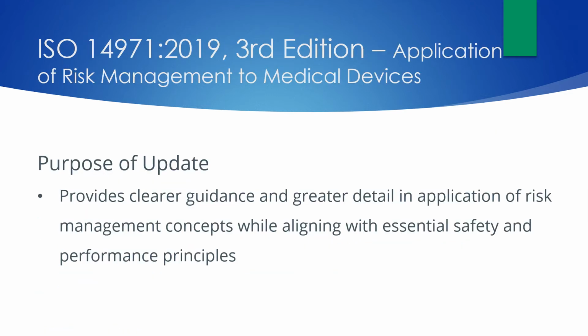The ISO standard 14971, which is the application of risk management to medical devices, was updated to its third edition in 2019. The purpose of the update was to provide clearer guidance and greater detail in the application of risk management concepts. It was not ISO's intent that the revision rework the risk management process, but instead aimed at clarifying the risk analysis process and specific steps device manufacturers must take. Another goal of the revision was to make it easier to update the standards guidance in the future without going through the entire process of changing it.